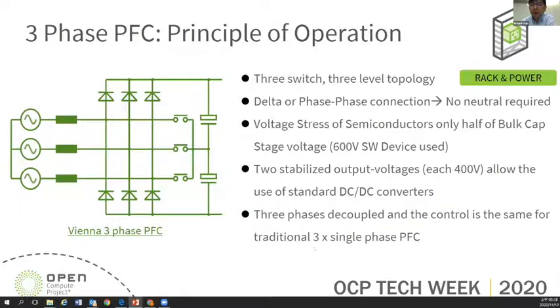And then we can have a brief introduction to this 3-phase rectifier. What we want to use is the Vienna 3-phase PFC. It utilizes a 3-phase bidirectional switch, and it is also a three-level topology. The input only has the phase-to-phase connection, no neutral winding. And we can also utilize 600 volt semiconductor devices. Since the output has a two-stage 400 volt, we can use the DC-DC converter with them to provide the output voltage. And the Vienna rectifier can decouple into 3 single phases, so the traditional single phase PFC control we can leverage from them.